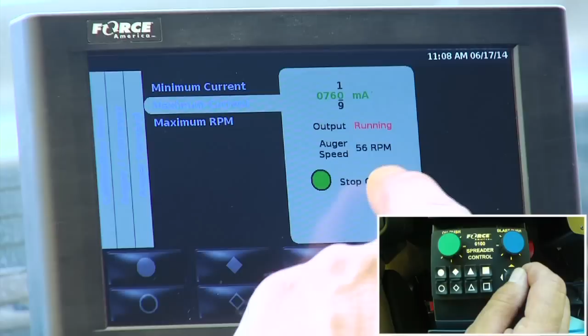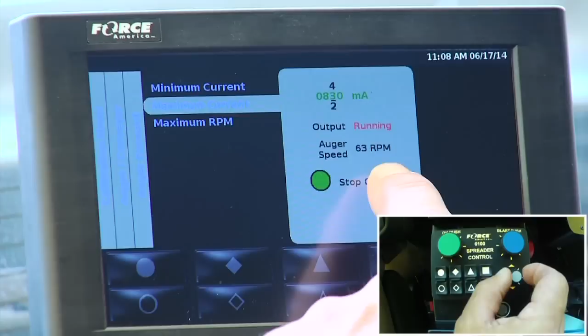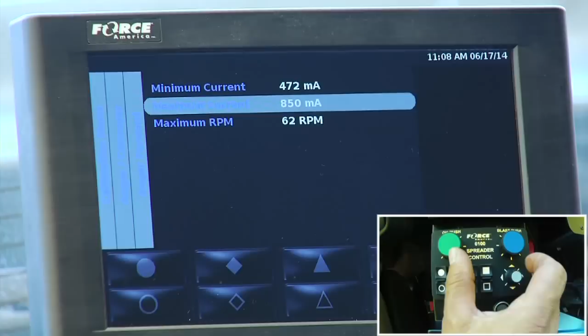I'm going to bring the milliamps down until the RPM starts to drop. Right now I'm at 63, 64, still up. Now I'm at 56, so it dropped. I want to get it back to that number of 65, 66. There, I'm at 64 - that's probably close enough, at 850 milliamps. So I shut it off.